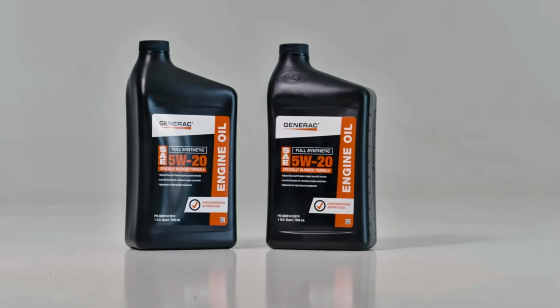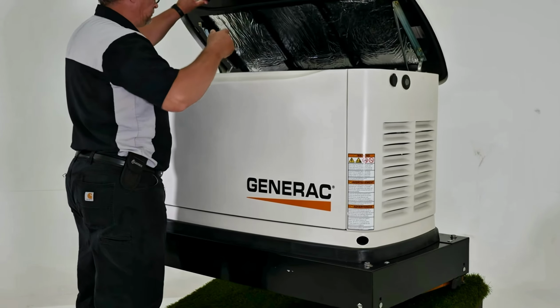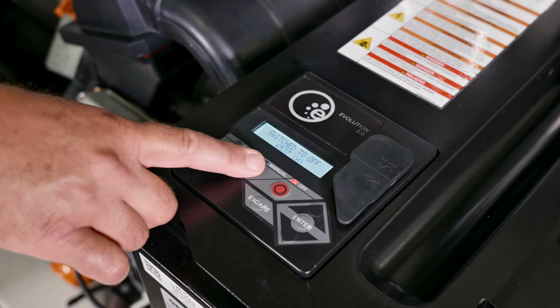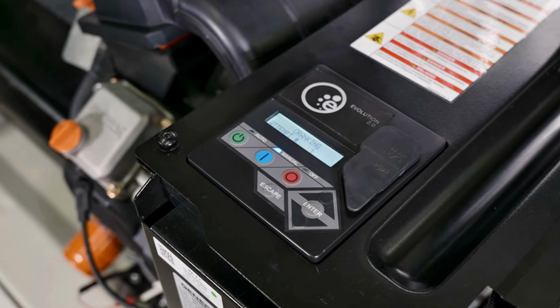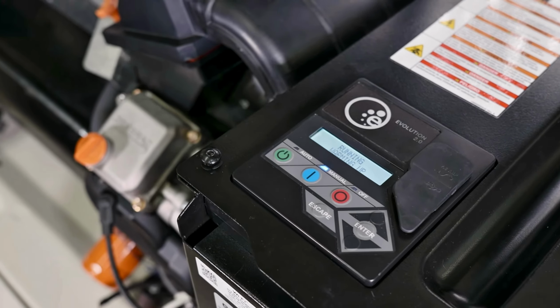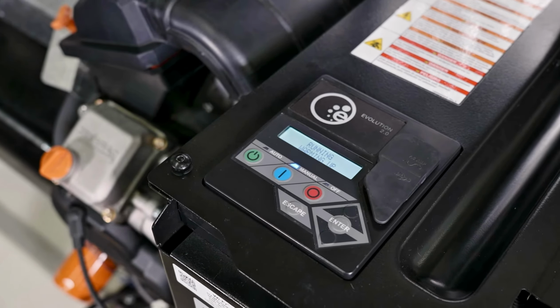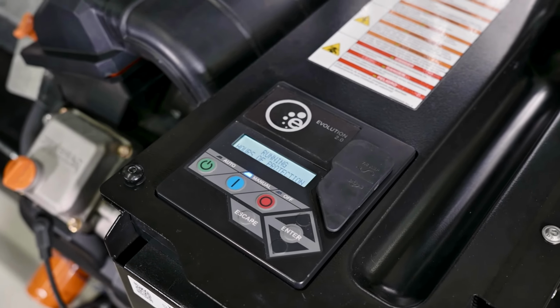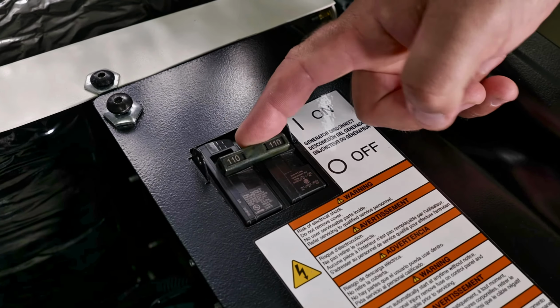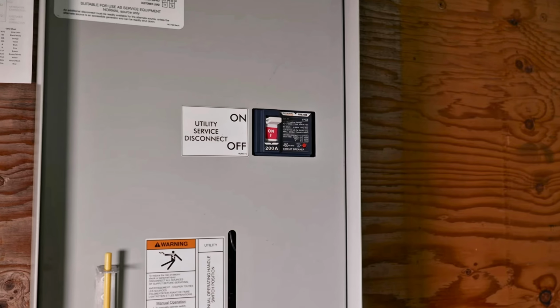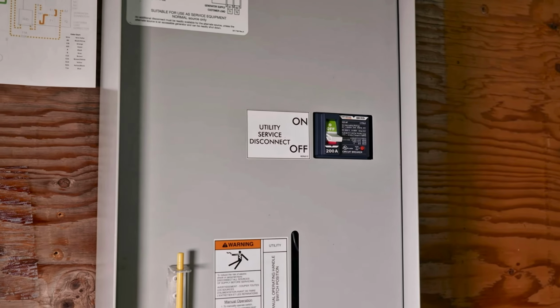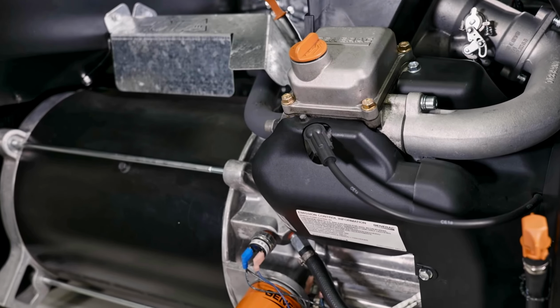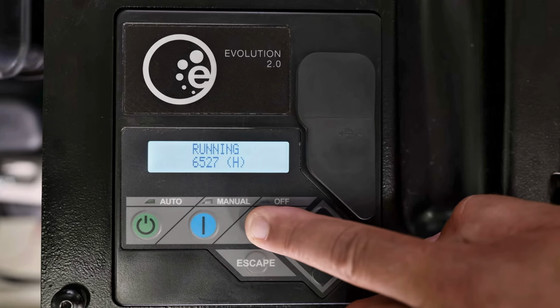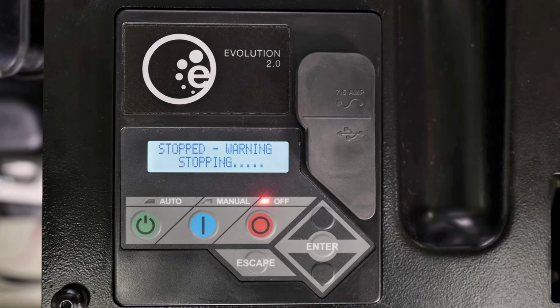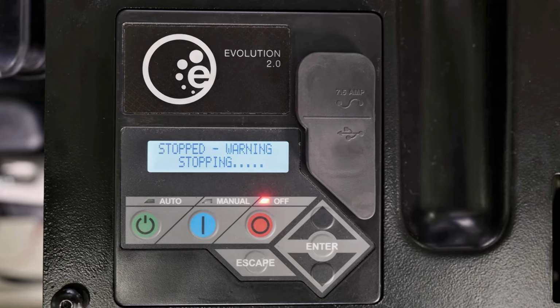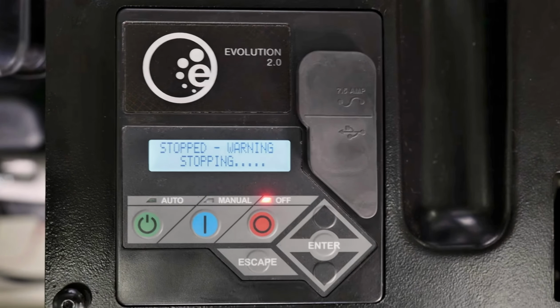To change the oil on your standby generator, first, lift the generator's lid and press the manual button on the control panel to start the engine. Let it run for 3 to 5 minutes until the engine is thoroughly warmed up. If running during a utility outage, set the generator's mainline circuit breaker to off. Set the utility mainline circuit breaker to off. Allow the generator to run and cool down for 5 minutes with no load applied. Then press the off button on the control panel to shut down the engine. Allow the generator to cool for another 5 minutes before working on it.